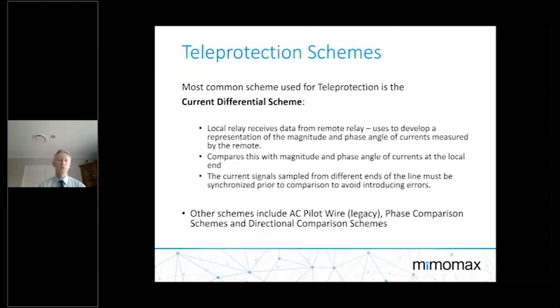The most common schemes used for teleprotection are current differential schemes. That's where the local relay receives data from the remote relay, used to develop magnitude and phase angle of the currents measured by the remote. This is compared with the local end, and the signals are sampled at each end of the line and synchronized prior to comparison to avoid introducing errors - making sure that time synchronization and symmetry at both ends of the communication system are aligned so we minimize any false trips.